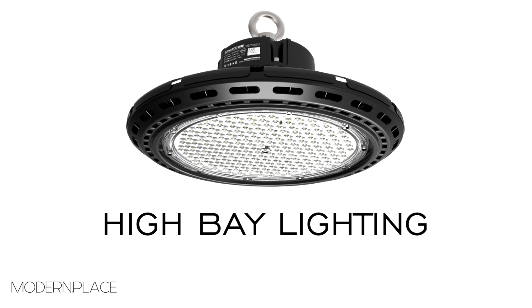In reality, you're getting about 135 to 140 lumens per watt with our lights, because there's the 5% net loss from the drivers, because there's no drivers on the market that are 100% power factor efficient, and if there are, they're exorbitantly expensive and probably fairly large. There's also another layer of lumen loss, or lumen depreciation, that happens through the diffuser and through the lifetime of the fixture. LEDs get less efficient as they go on throughout their lifetime. That's why we go with the DLC Premium mark, which guarantees that our fixtures are going to be 90% efficient or more at the end of their lifetime.